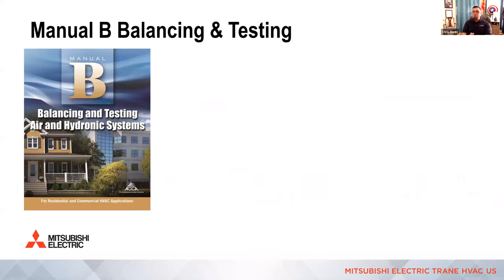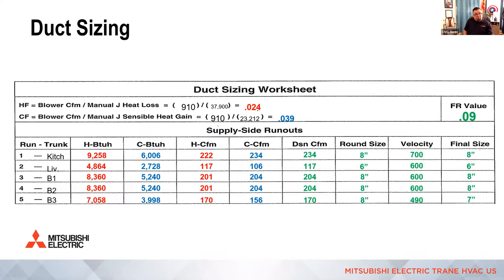All right, once we have all the runs, sizing the trunks is actually really easy. For time purposes, I didn't include this in the presentation, but you can see there's another section on the bottom for sizing your supply and return trunks. If you follow the rules of duct design I'm about to walk through, it becomes very obvious. Basically, after every 2 to 3 takeoffs, you want to see how much volume of air is left. Check your velocity. When it gets below 700 feet per minute, you downsize your trunk to get the velocity back up for the remaining volume of air going to those spaces. All right, so pretty simple.